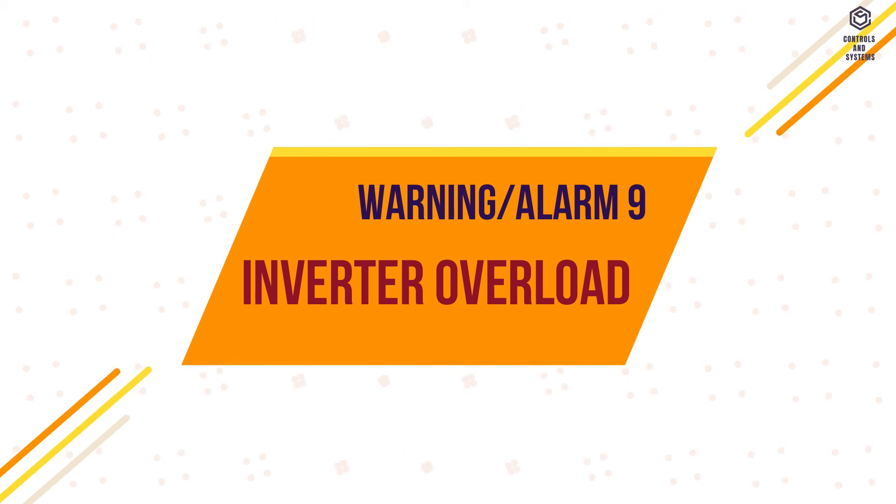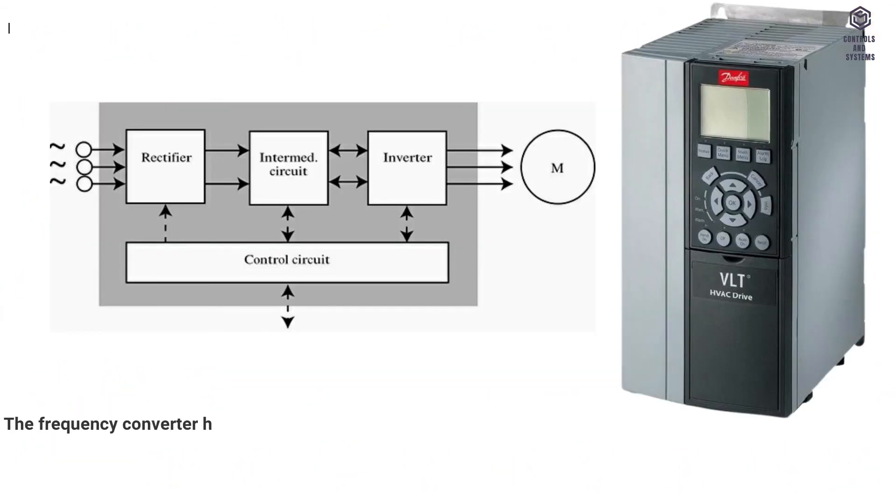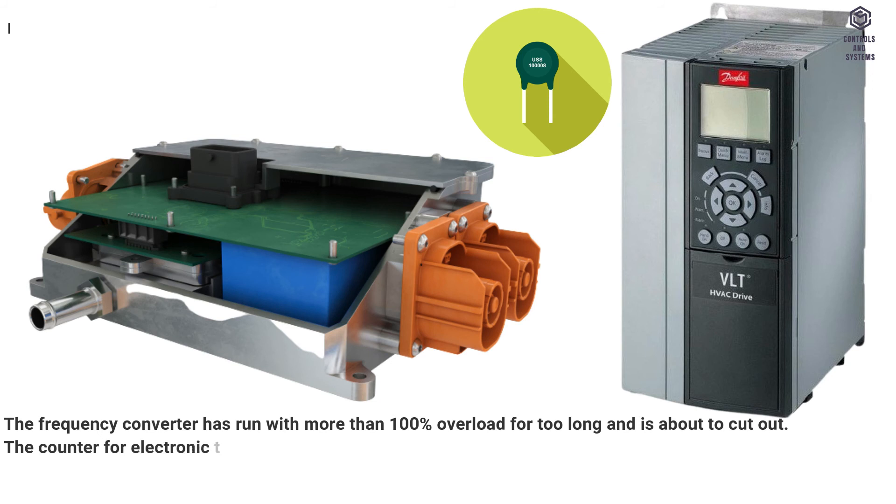Warning, Alarm 9, Inverter Overload. The frequency converter has run with more than 100% overload for too long and is about to cut out. The counter for electronic thermal inverter protection issues a warning at 98% and trips at 100% with an alarm.